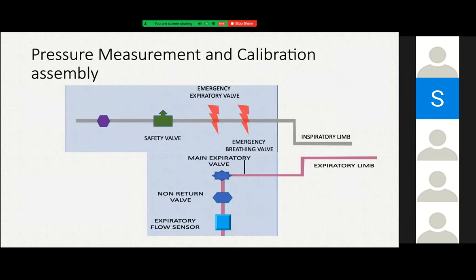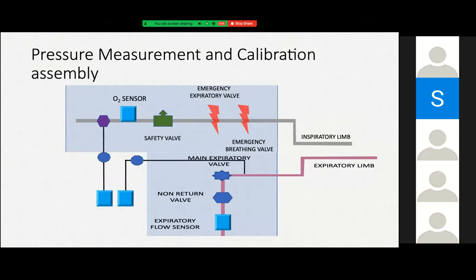In addition to the mechanical parts, we need sensors to regulate and sense flow and FiO2. We have an oxygen sensor in the inspiratory limb which senses the oxygen concentration. We also have pressure calibration valves and pressure sensors which sense pressure in both the inspiratory and expiratory limbs.